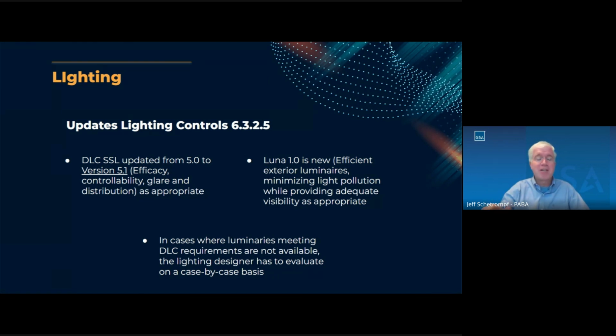This is the third party thing that's verifying that we're actually going to get what we want. There are literally hundreds of thousands of items listed under these DLC criteria, so there's really no excuse not to comply with the requirement where the fixture is covered. That brings up our last point on this slide: DLC ratings don't cover all lighting categories. One that we hit upon a lot is decorative fixtures. In those instances, the project's lighting designer must evaluate on a case-by-case basis to ensure that the lighting quality and efficiency levels are being met in accordance with P100 requirements.